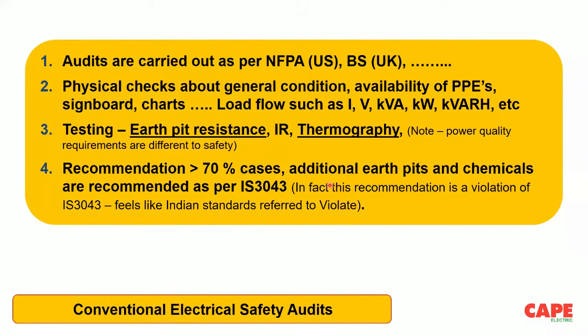additional earth pits and chemical earths are recommended. And the sad part is it's always recommended as per IS 3043. As a member of ETD 20, I know very well that this chemical earth or this additional earth pit is not going to help you. So if anybody wants to recommend a chemical earth pit, you recommend. We have no issue. But the problem is, don't claim that it is as per IS 3043, because IS 3043 was never written in this fashion.